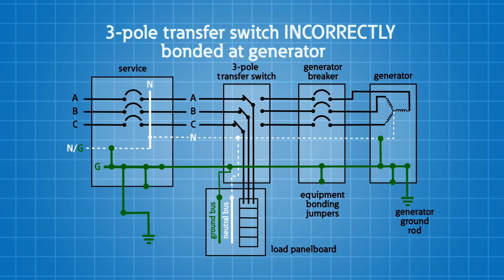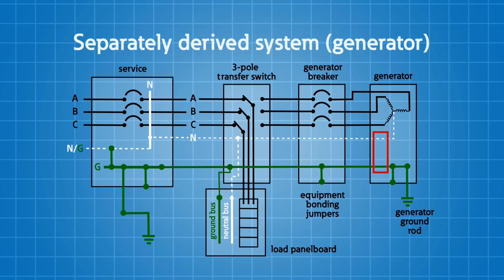You could cause GFCIs or ground fault protection of equipment not to work and function correctly. A simple fix, if you didn't buy the right transfer switch, a 3-pole transfer switch, and you bonded that neutral in the generator, is to just lift the bond in the generator. Your generator instructions will tell you how to do that.